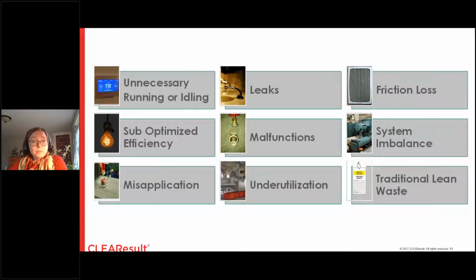Or maybe you're a commercial office building and you've got an outside air temperature sensor that is controlling your whole building automation system. That thing is telling all your economizers when to open and close. It's telling your chillers whether they should come on or not, your boilers whether they should come on or not. And that sucker's 10 degrees off. Whoops. None of those decisions are going to be made in an efficient way because of one silly little sensor that was wrong. So be very aware of malfunctions. They can really bite you in a way you don't expect.